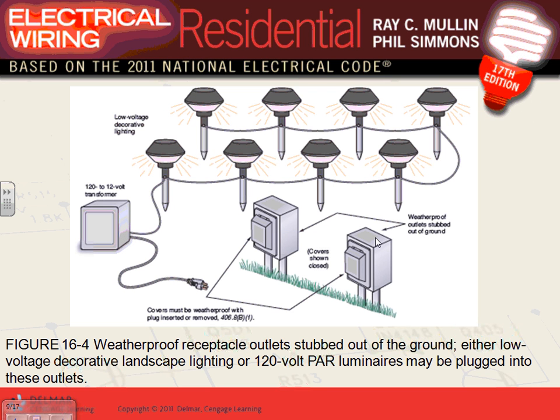Okay, here's what we're talking about, guys. You're going to have a 120 volt to a 12 volt transformer. You plug it into a GFCI protected in-use cover, right? The weatherproof receptacle, and then you feed all your stuff. Now, the problem with my friend here is he was tying the hot and the neutral, shorting at this point. If you short at this point here, at 24 volt, guys, the circuit breaker that protects this whole equipment is not going to wake up fast enough before the smoke starts coming out of this baby.